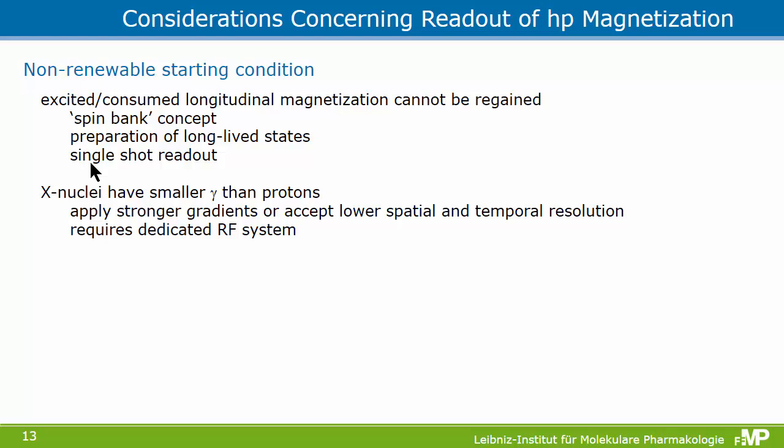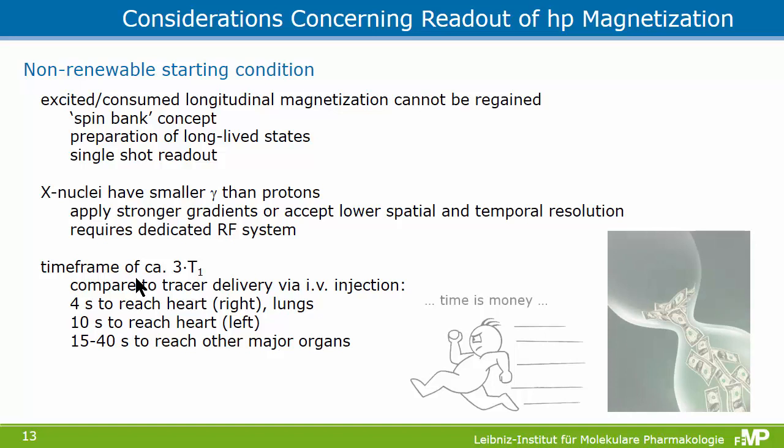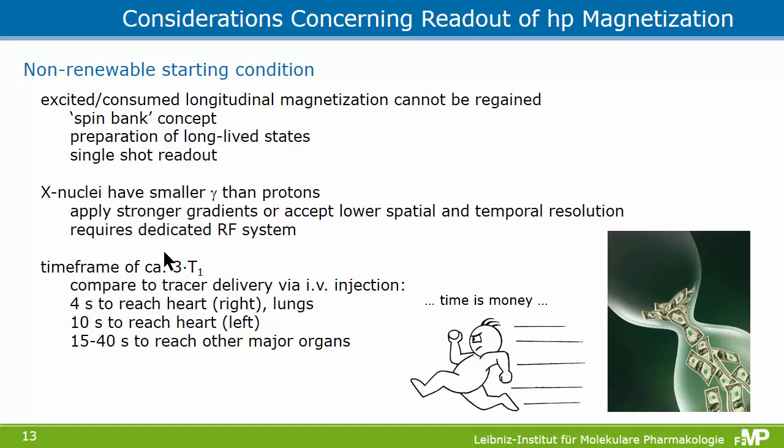Another aspect is that if you go away from water and want to detect nuclei other than protons, these nuclei have a smaller gamma than protons. If you want comparable resolution you need stronger gradient systems. While this may not be a typical problem since you work with larger pixel resolution, it at least requires a dedicated RF system operating at the frequencies of these X nuclei. And of course, one important aspect in hyperpolarization is that time is money.